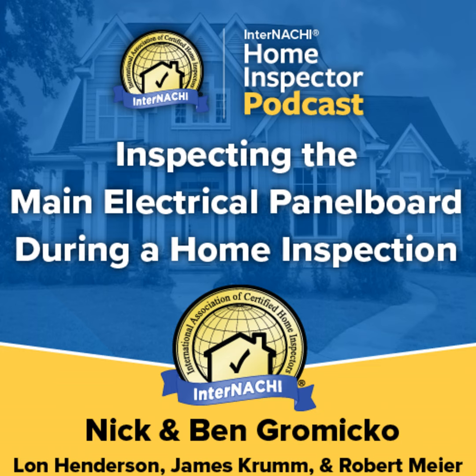Breakers that have handle ties that cause both handles or toggles to move together are considered one throw. The NEC requires no more than 6 breakers, or throws, to completely turn off the power to a panel and home. This is called the 6 throws rule, which means that no more than 6 hand motions will turn off the whole panel. An inspector should never see more than 6 breakers to turn off a panel. As of the 2020 NEC, services must have one main disconnecting means.